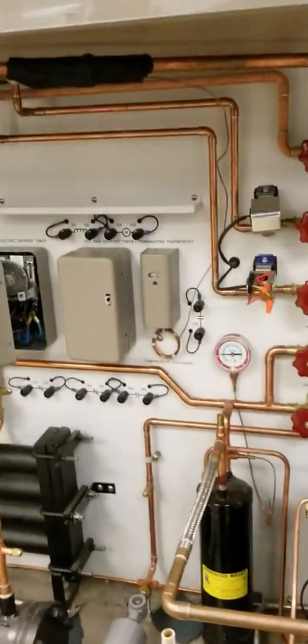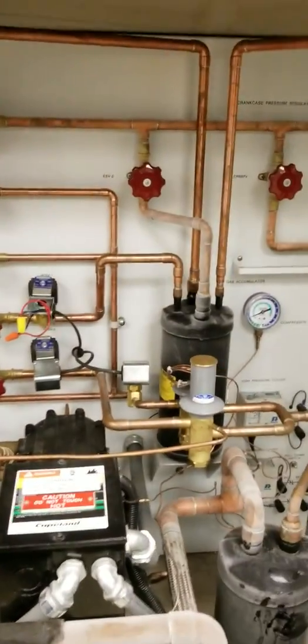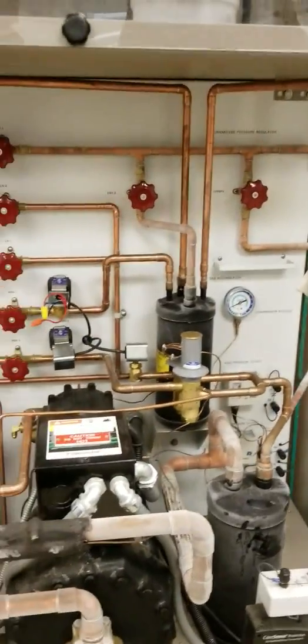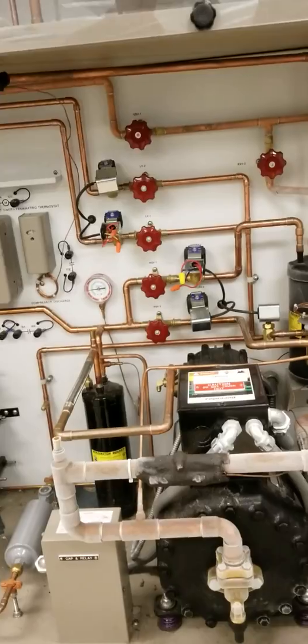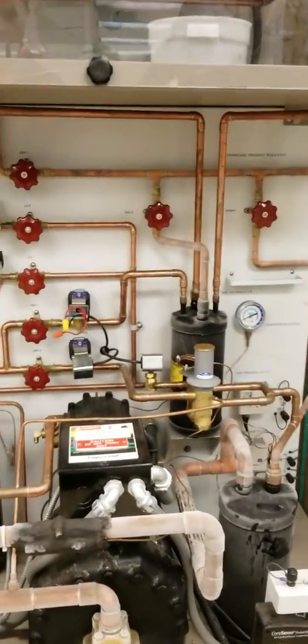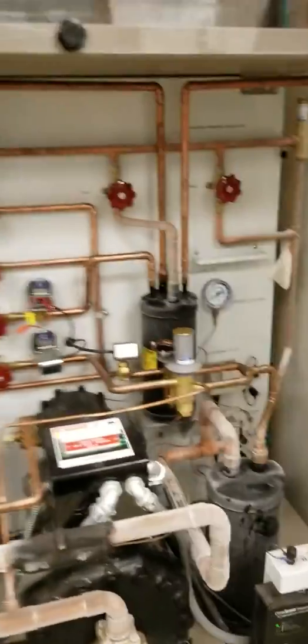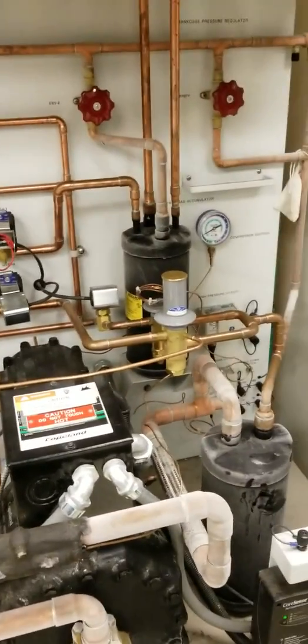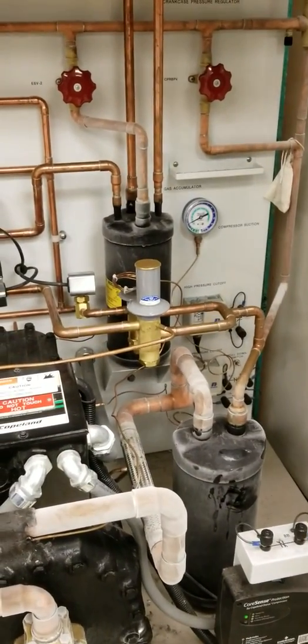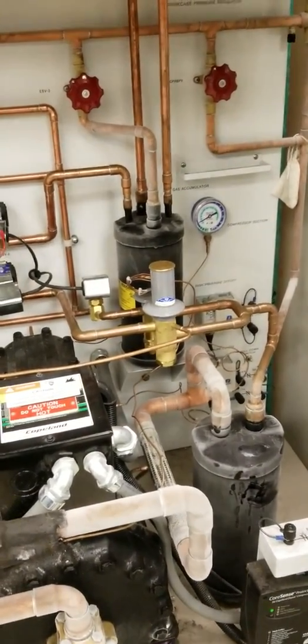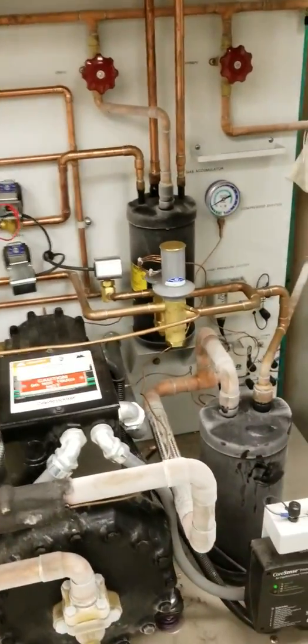Okay, so you have gauges permanently installed. So all you would need to do is take the clamp to it. Yeah, just to tell. Okay. And then you can tell your subcooling and your superheat. Yep. Right, that's the only way you have to verify it. There's nothing in the system. I mean, I don't think they're far off, and maybe the more advanced systems actually do have temperature sensors that do those calculations, and they tell you those numbers, just like digital gauges do. But for now, we have to manually do it. Okay.